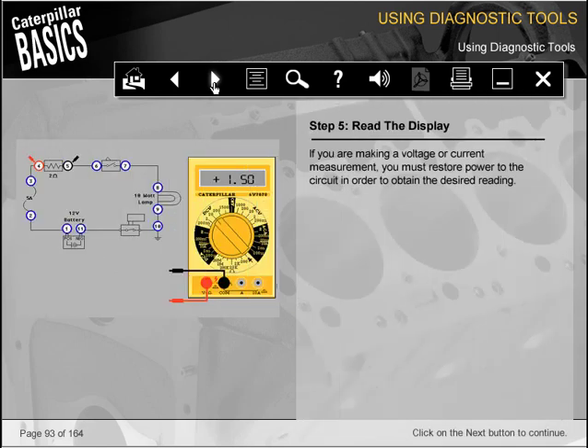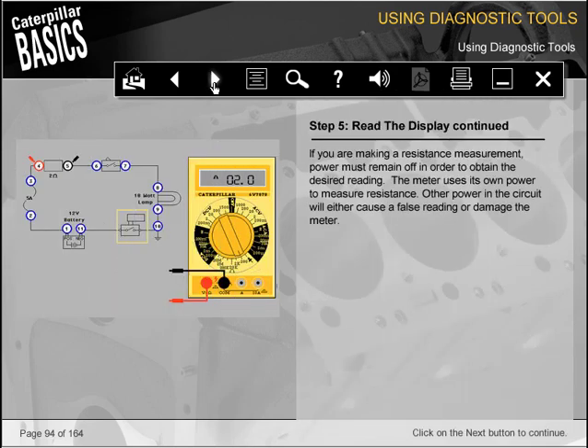If you are making a voltage or current measurement, you must restore power to the circuit in order to obtain the desired reading. If you're making a resistance measurement, power must remain off in order to obtain the desired reading. The meter uses its own power to measure resistance. Other power in the circuit will either cause a false reading or damage the meter.